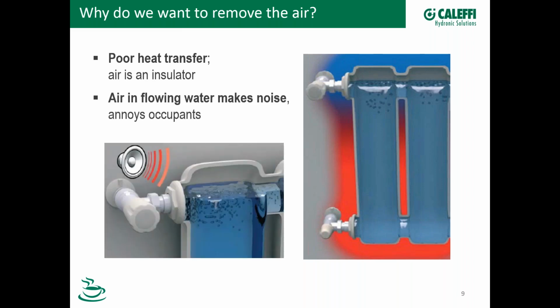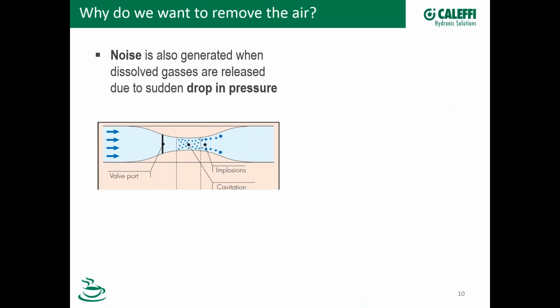Air is a problem for more than one reason, but primarily it makes noise and can annoy occupants. And the important thing to know is that once you get all the air out of a system, a good hydronic system that's air-free is silent. So speaking of air, another source of noise is cavitation. And cavitation is generated when dissolved gases are released.